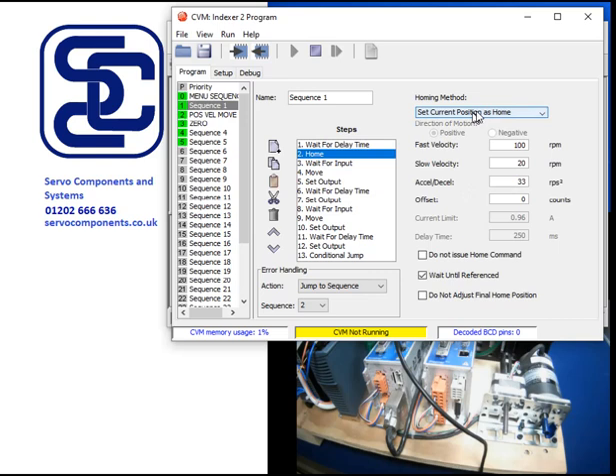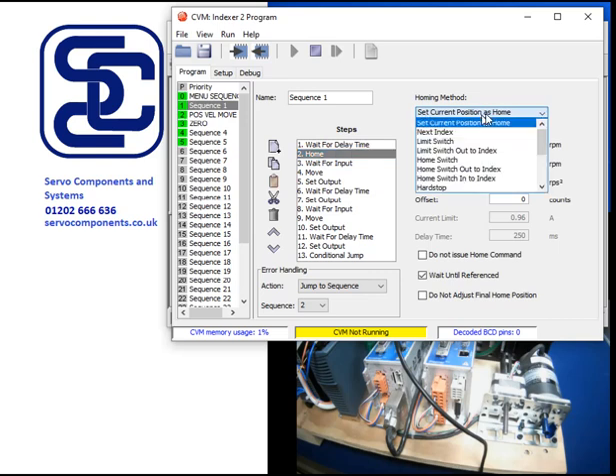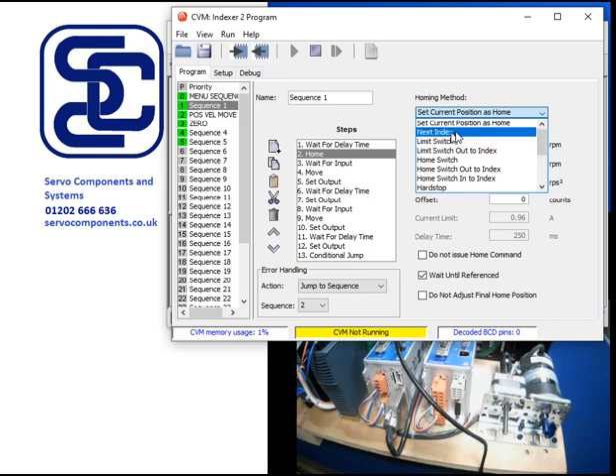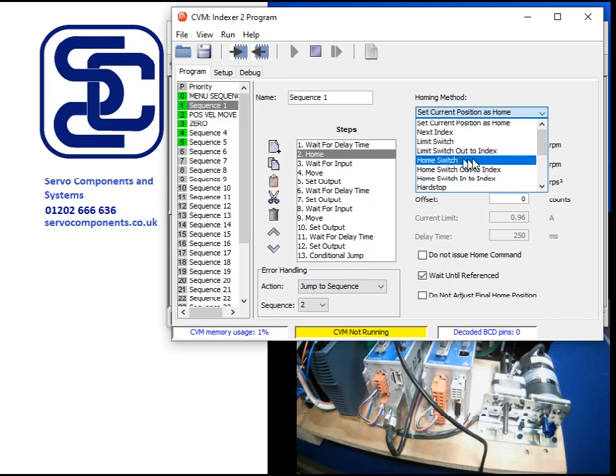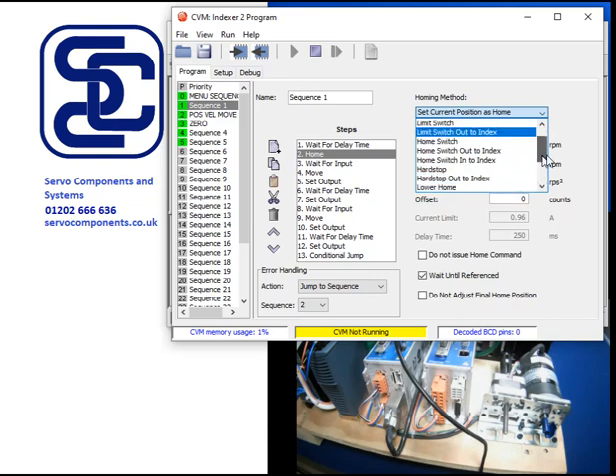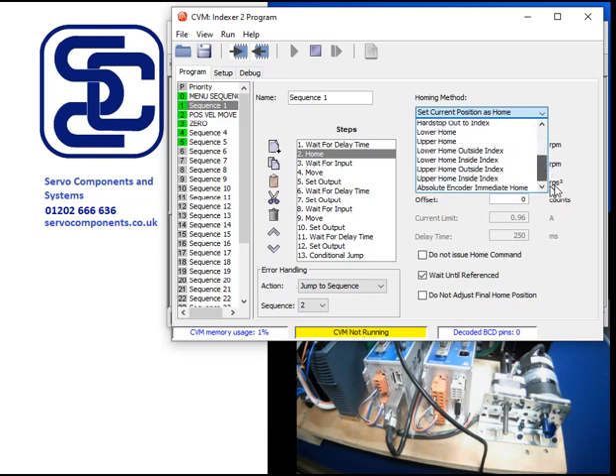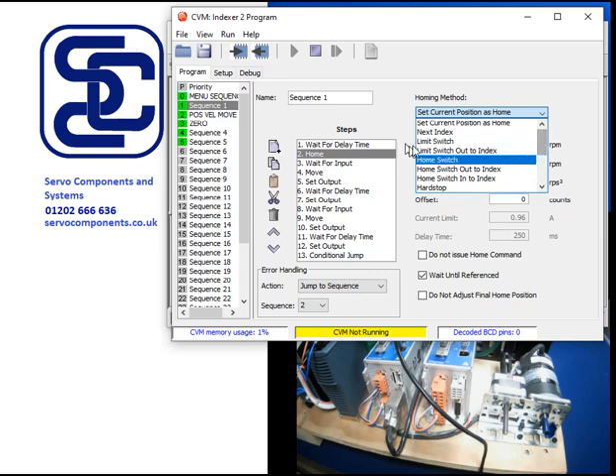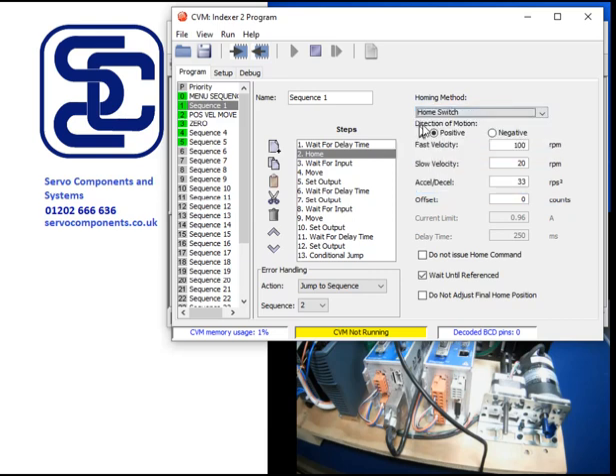Now we do the move. And we can either set the current position as a home, the next index position - if it's a linear system you can move to the next position on the index mark. And we can move to a limit switch, a home switch, a hard stop, various other options there. So I'm assuming we've got an incremental encoder and I'm going to move to the home switch.